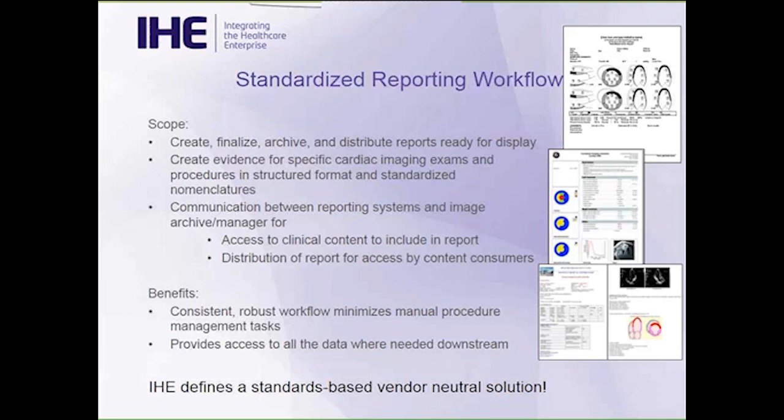The capture of cardiology-specific content as DICOM structured reporting evidence to be included in clinical reports is defined as a specialization of the evidence document profile from radiology. So we've extended it in order to support the cardiac-specific content.